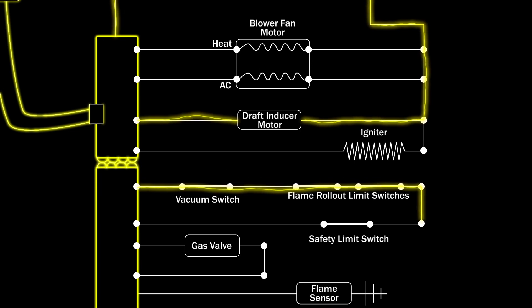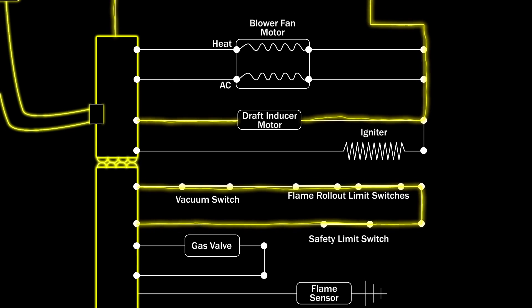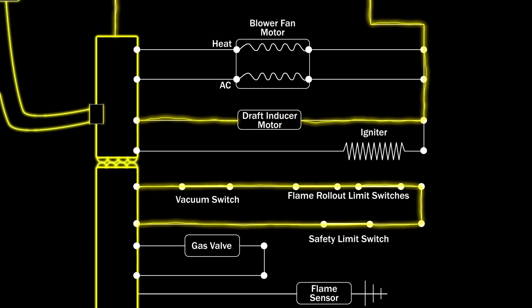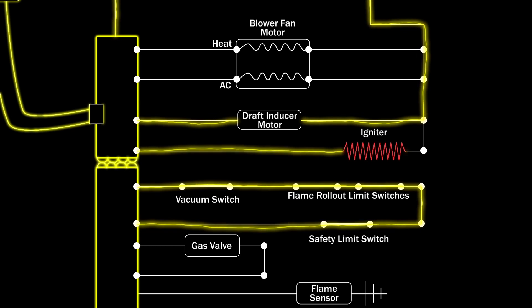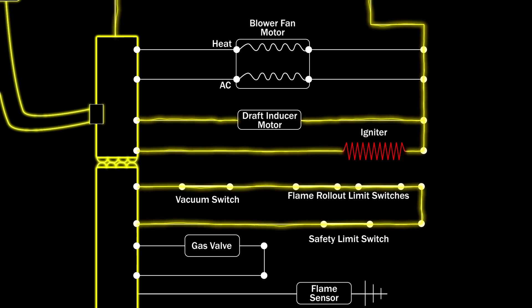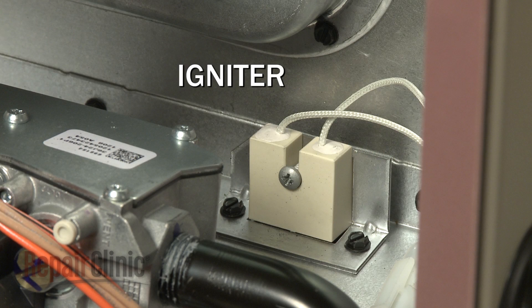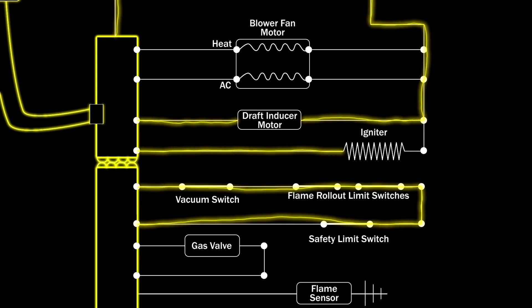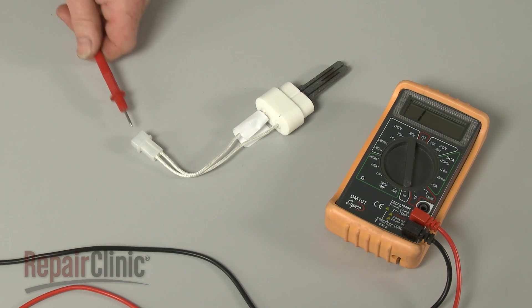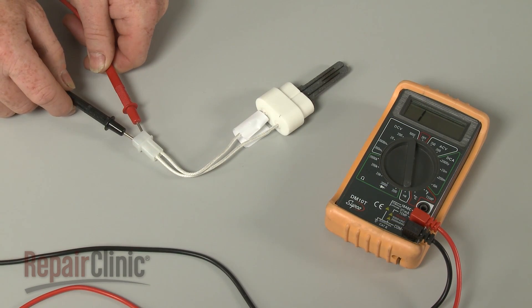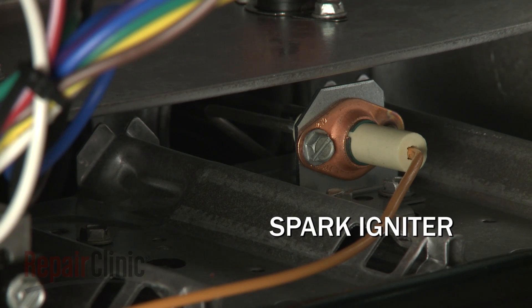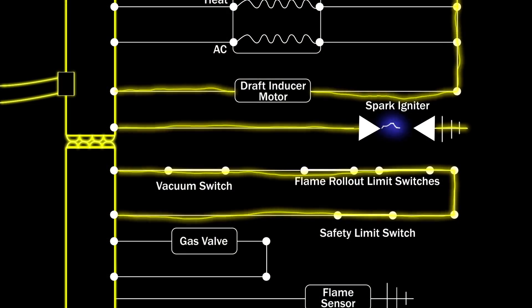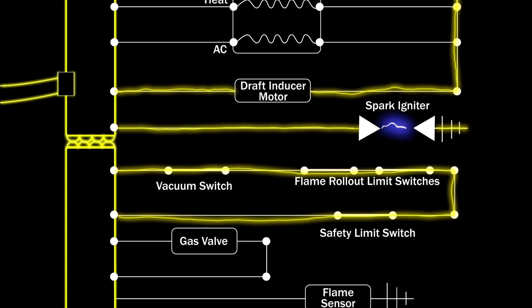Once the vacuum switch closes, 24 volts will travel through the switch and one or more limit switches, allowing the control board to continue the startup. The control board now sends 120 volts to a glow bar style igniter, depending on the model. A defective igniter will halt the ignition sequence and prevent the furnace from heating. A glow bar style igniter can be tested for continuity to help determine if the part is functioning. Be aware that some models will use a spark igniter instead. Spark igniters will also receive voltage from the control board, but the amount of voltage is greatly increased and will pulse to create the spark.